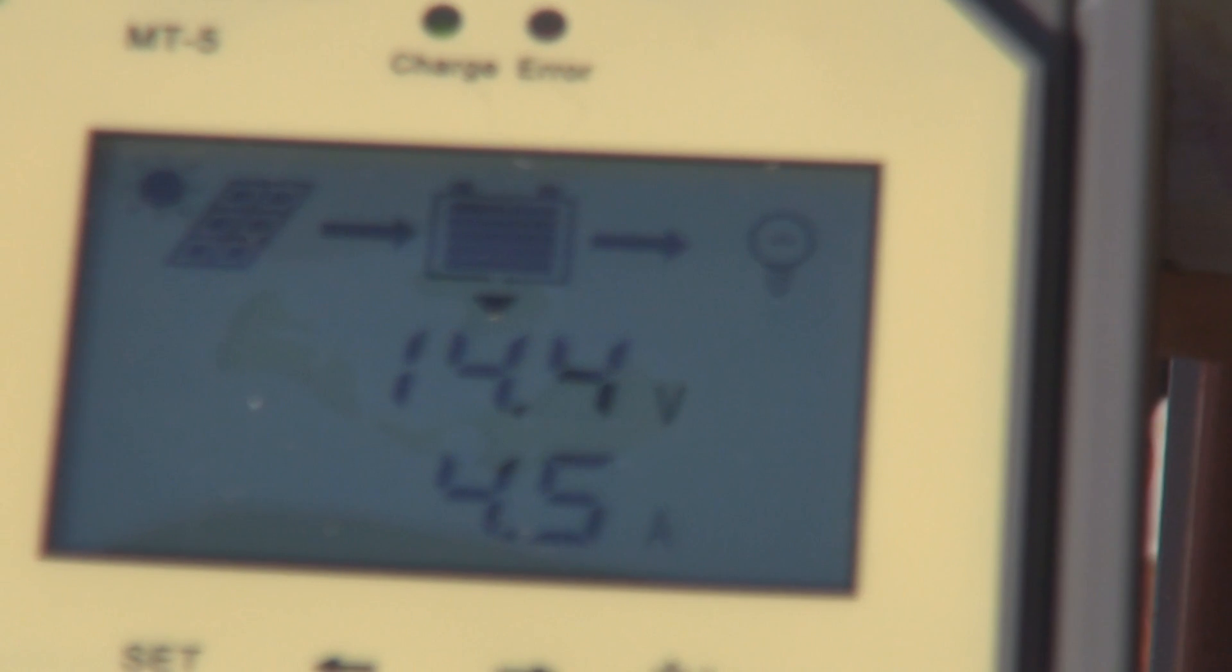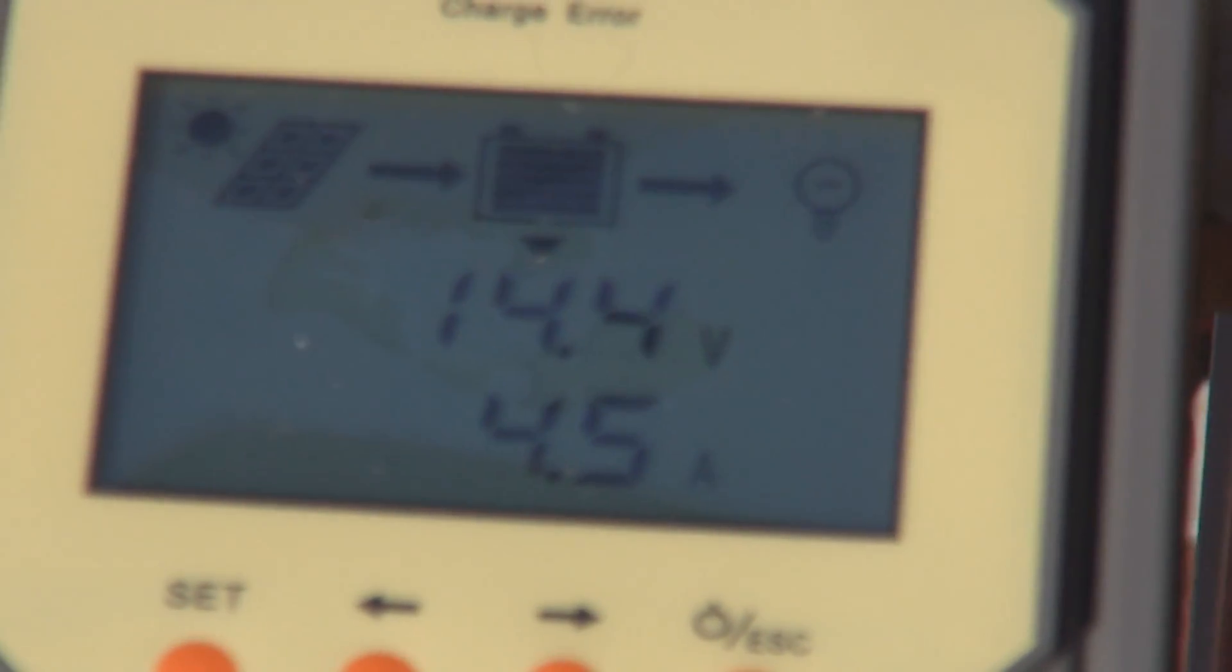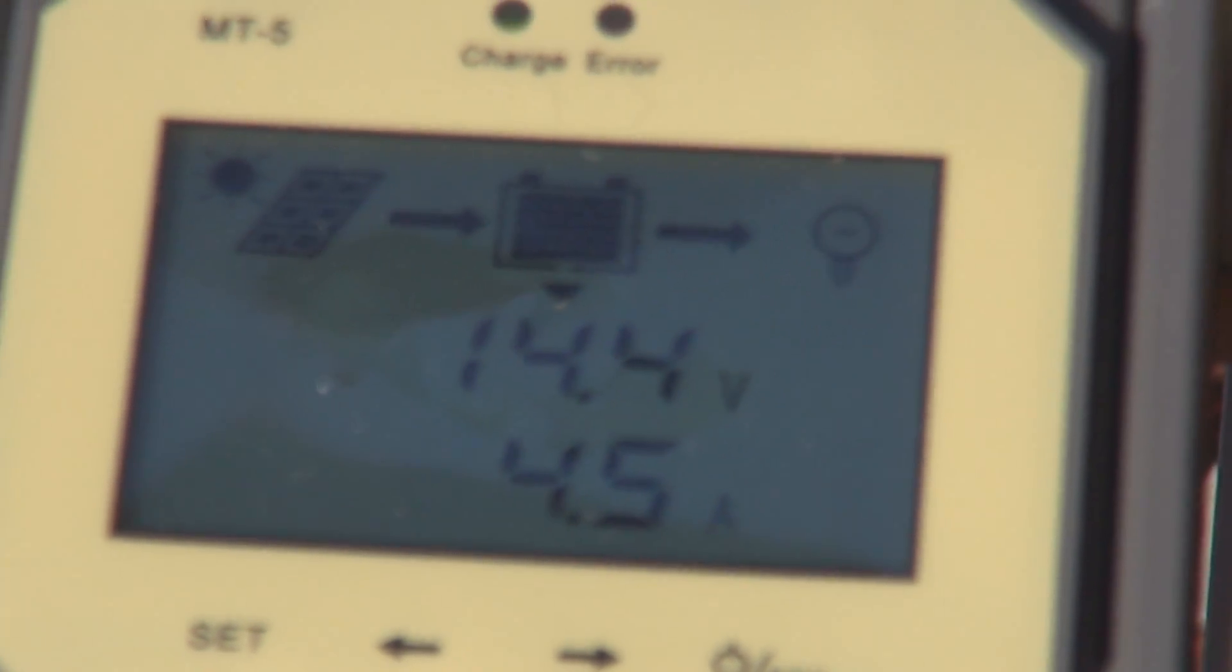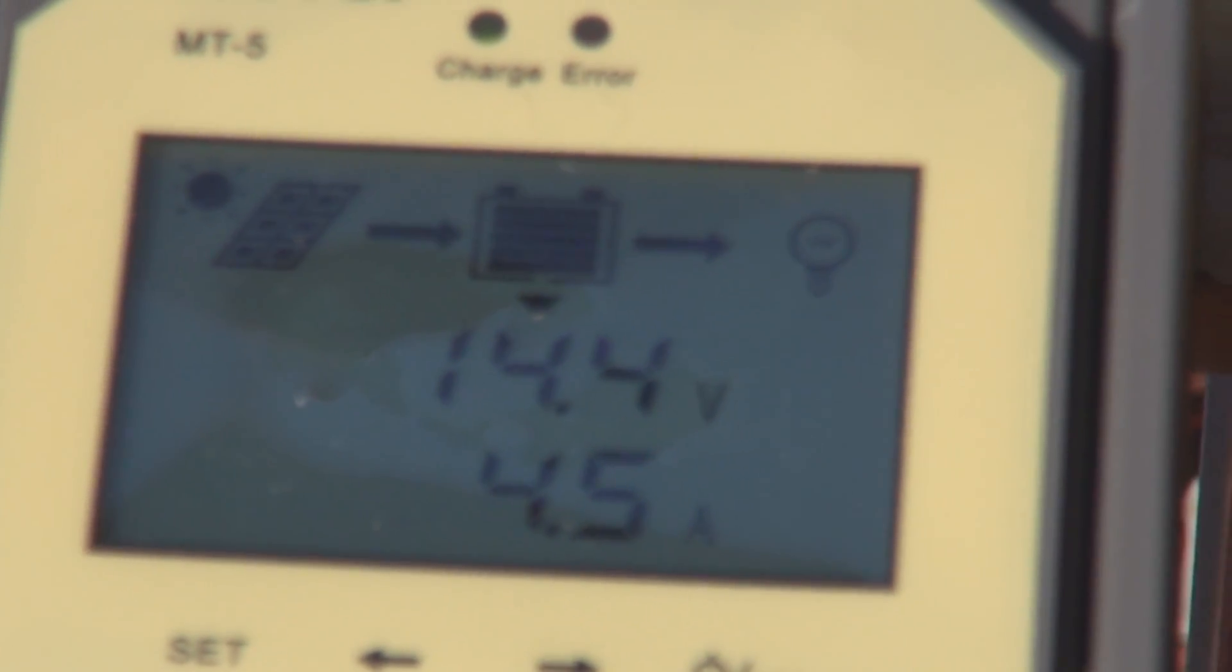The charging side of the controller will push this battery at 14.4 volts for about 2 hours before bringing it back down to a float voltage of 13.8 volts.